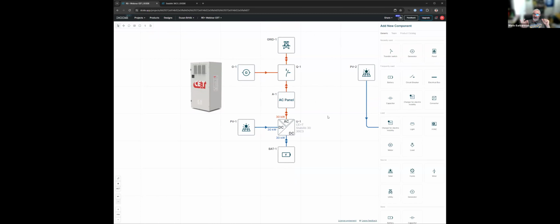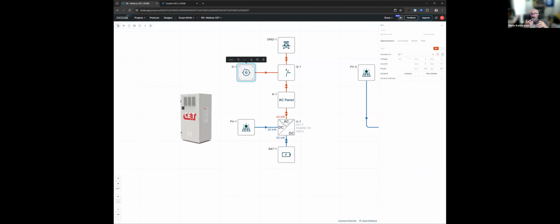So in our science, we call that leading power factor. You have to decide who's leading and who's lagging. And we always have to keep in mind that a generator is not meant to be lagging. If suddenly the generator considers and measures itself like a load, the governor on the generator will shut everything down. You could be in a very bad situation where you need that power, and suddenly the generator goes down, because the generator sees itself as a load and disconnects and shuts down.